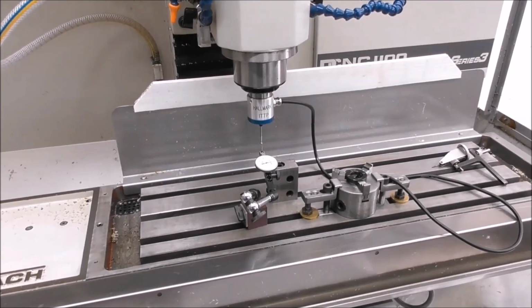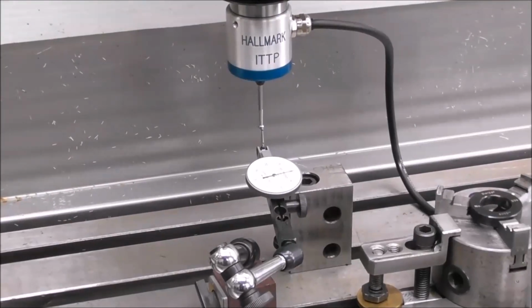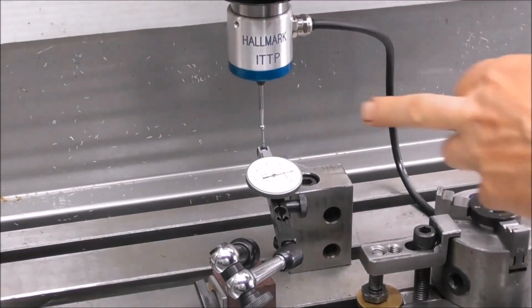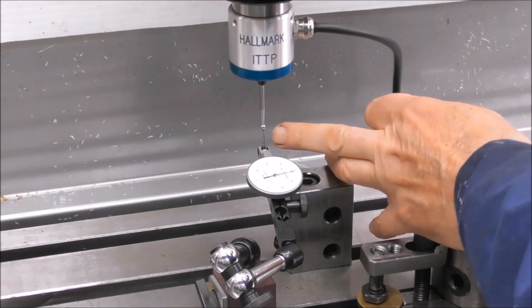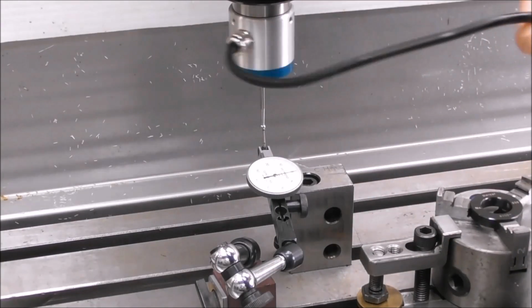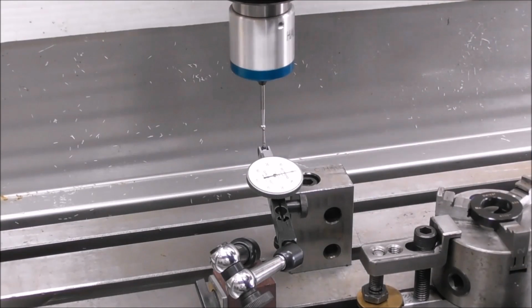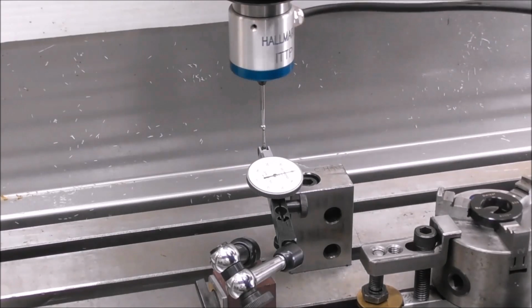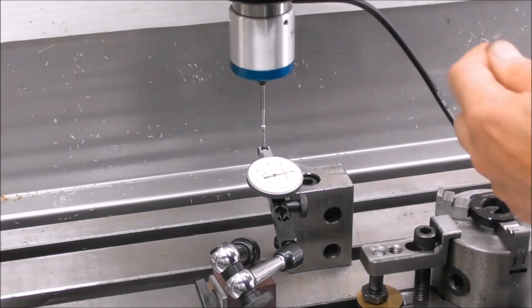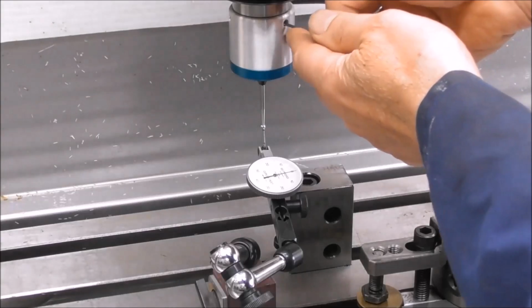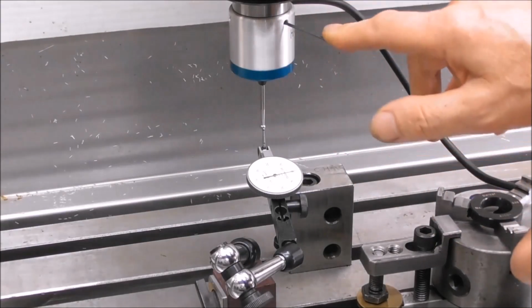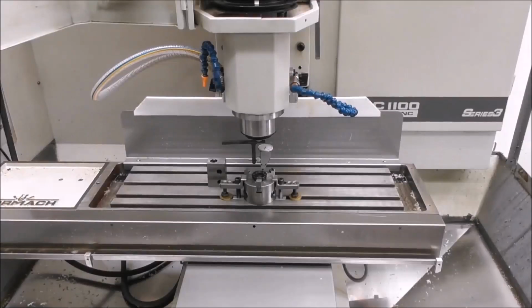And again, checking the calibration of the touch probe in a similar way. We've got a dial test indicator on the stylus tip, and we're just rotating it around there. Again, we're not worried about microns. We've got it within about 1/4 of a hundredth. The adjustment is made in a very similar way with little grub screws here at the top.